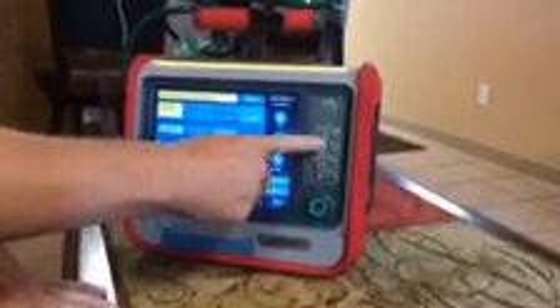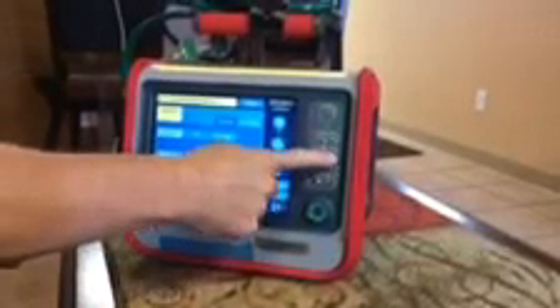If you're working with somebody and you don't want them to mess with your ventilator, you can actually lock the screen and unlock the screen with this button to the right. If you want to do an inspiratory hold on your patient, I really can't think of a reason why we would do that. You can hold this button and it'll provide you an inspiratory hold until you release that button. Over here, the oxygenation button: if you're getting ready to suction your patient and you wanted to do 2 minutes of 100% oxygenation, to pre-oxygenate your patient, you push that button and it'll provide you 2 minutes of 100% oxygen. And this button down here is for the nebulizer function, and I'll show you in a minute.